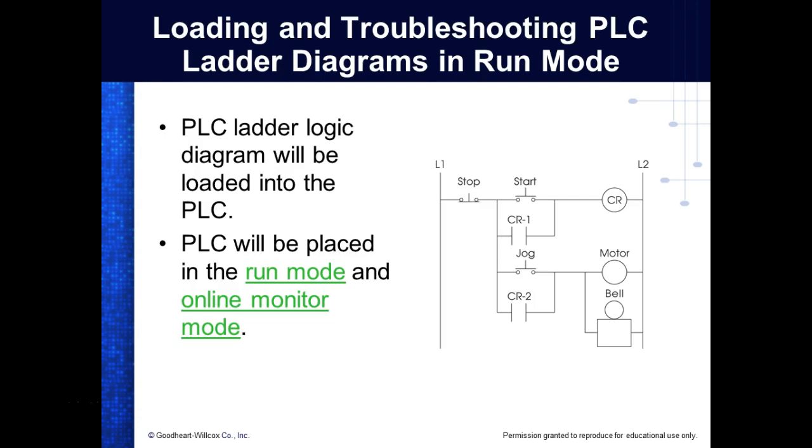And I'll also show y'all some of the PLCs actually have a switch on it. They got a key in there, and you got 3 positions. You have program, which is kind of misleading. That's where you can upload and download programs on it. Then it's got remote, which is what this guy is automatically. It means you switch it between the modes with your computer. And then it's got the run mode.